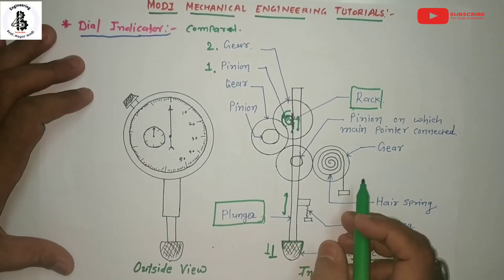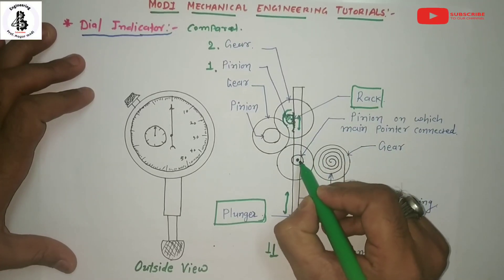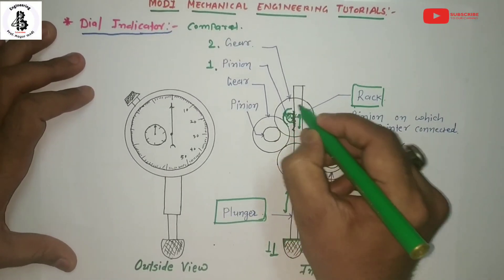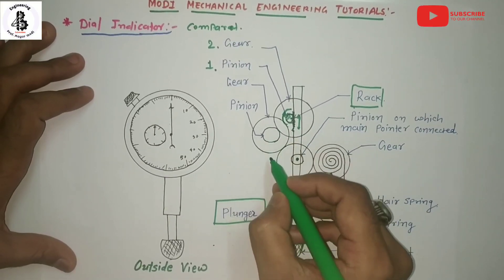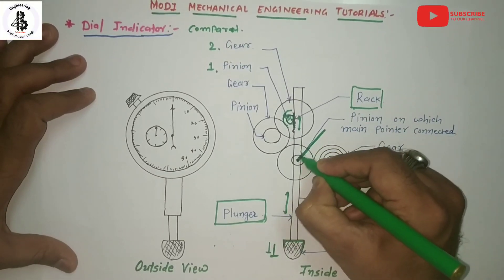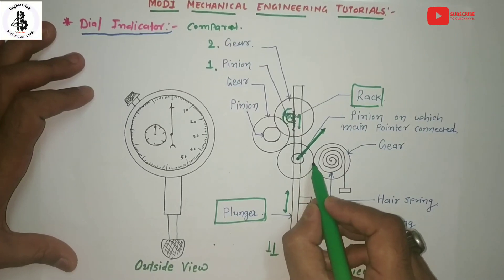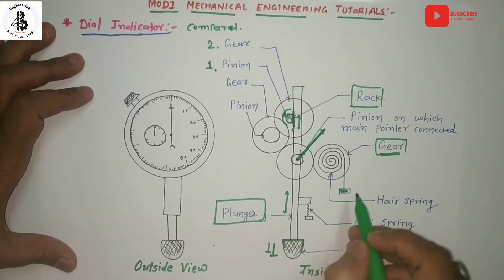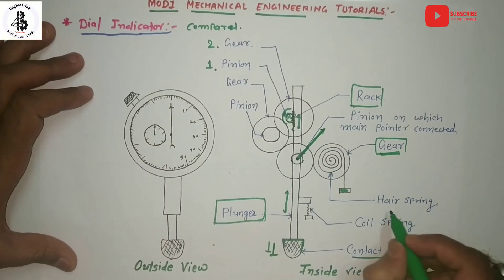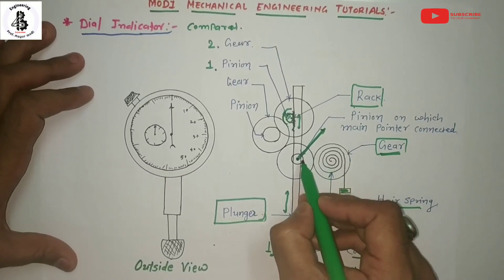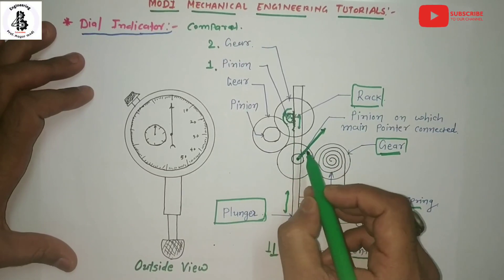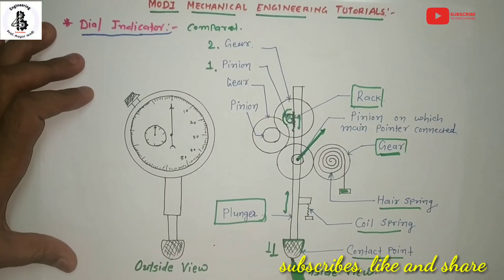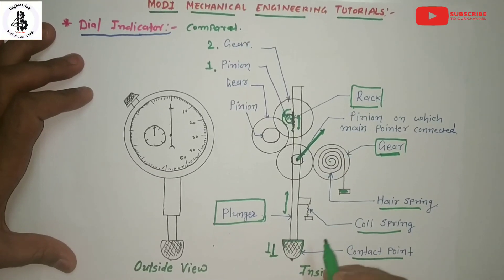Finally, the pointer is attached onto the final pinion, and according to that movement the pointer rotates. The pinion is also connected with a gear mechanism. When the load is removed, the hair spring returns the pointer to its initial position. The coil spring ensures that when the dial indicator is positioned against the measured surface, it returns to a stable condition, giving a zero reading.